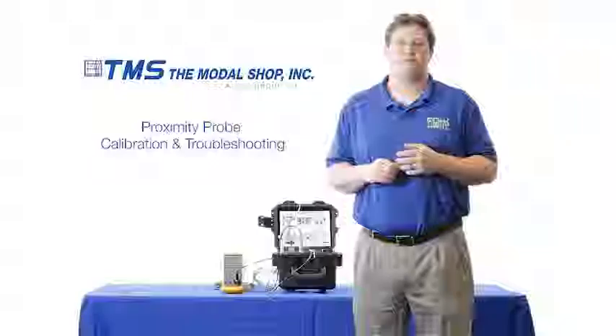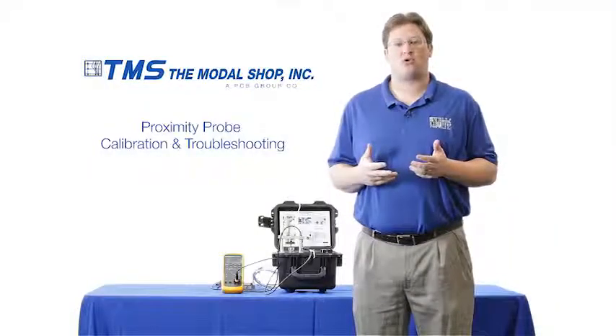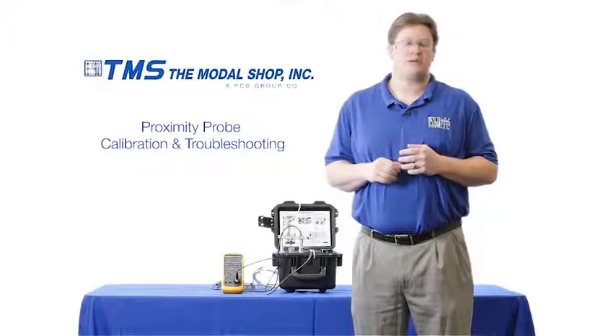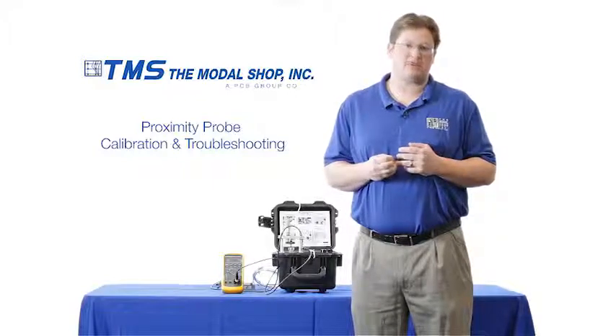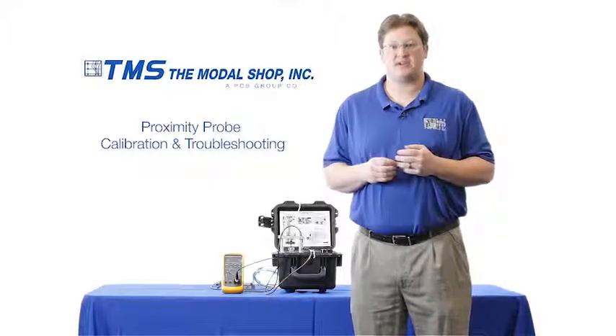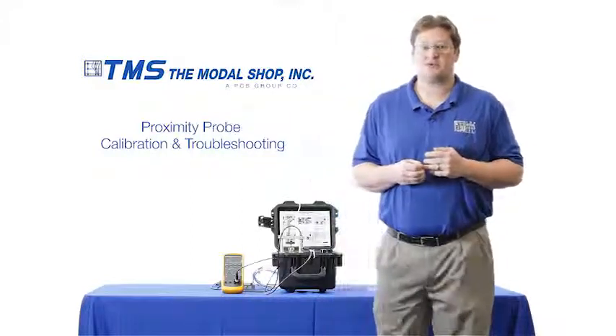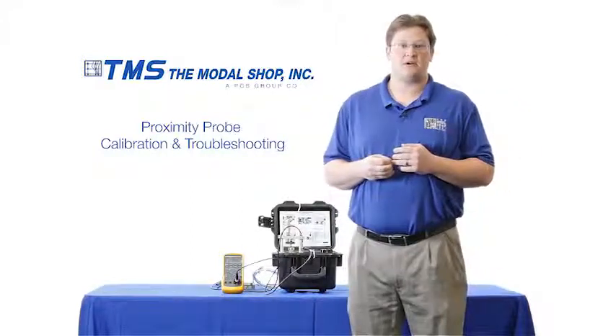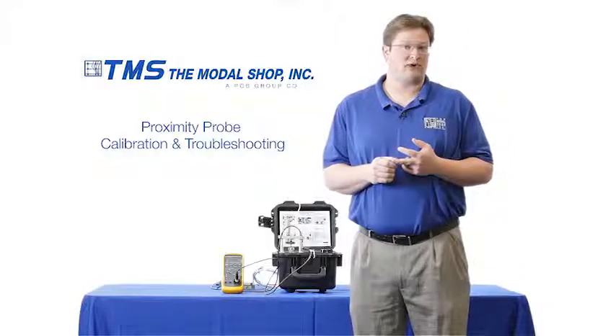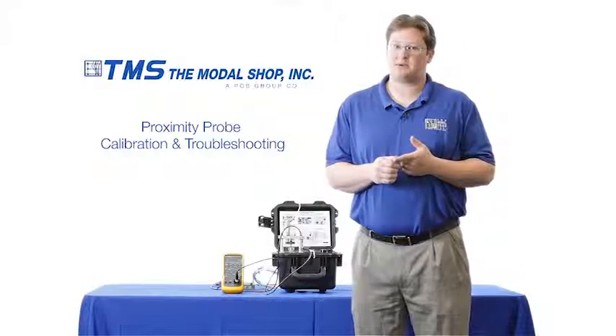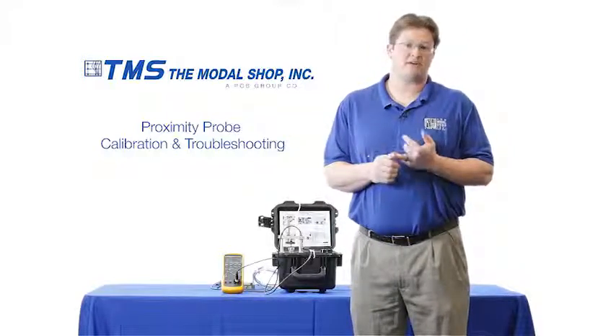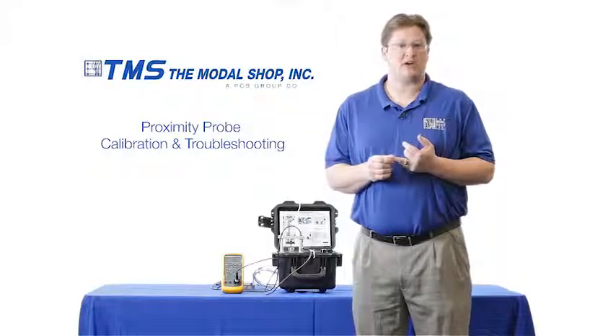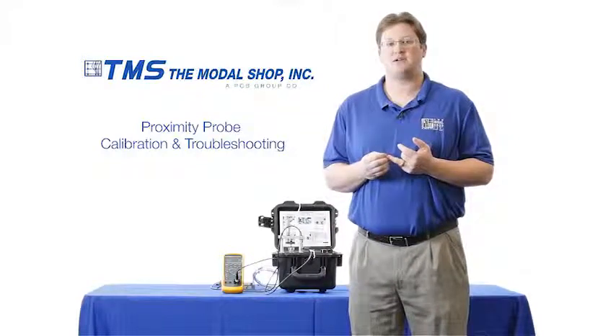So now you can see how the Modal Shop portable vibration calibrator can troubleshoot proximity probe cabling issues that sometimes gap voltage can't detect. Not only is it a great troubleshooting tool, it's easy to use. The proximity probe needs to be mounted only once. The exact displacement can be read on the display, and the exact speed of the machine can be simulated by changing the cycles per minute or the frequency in hertz.